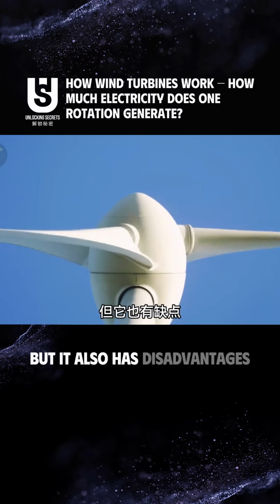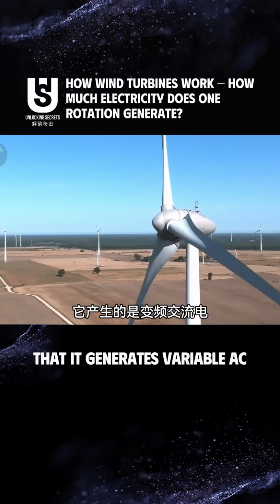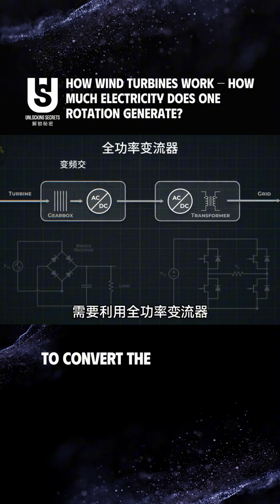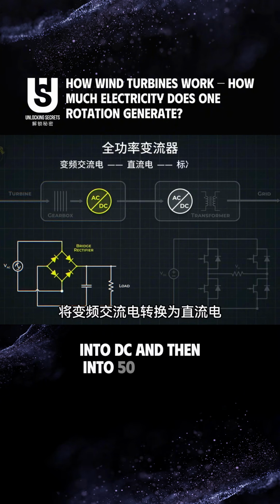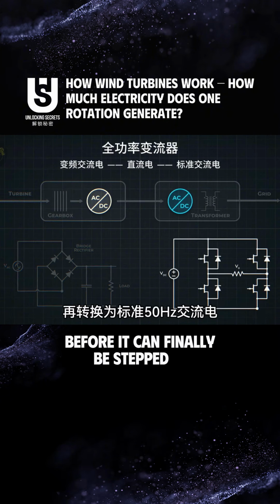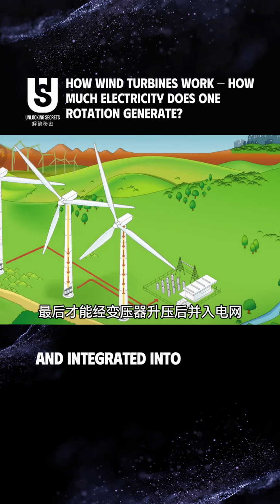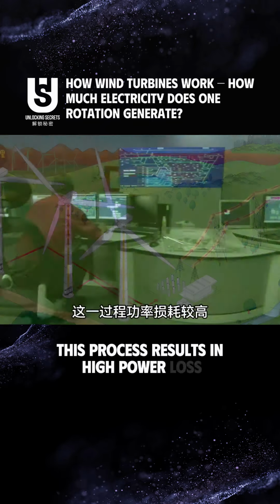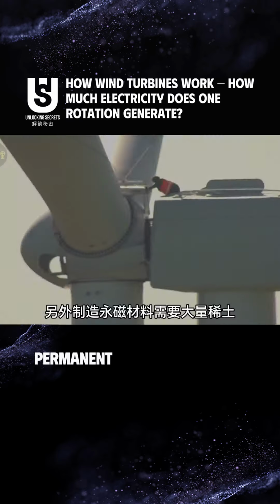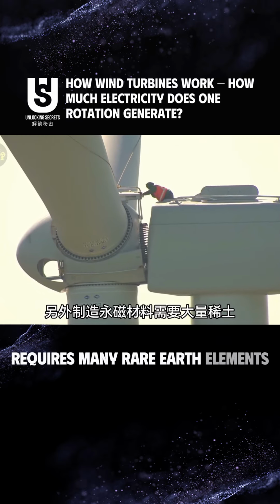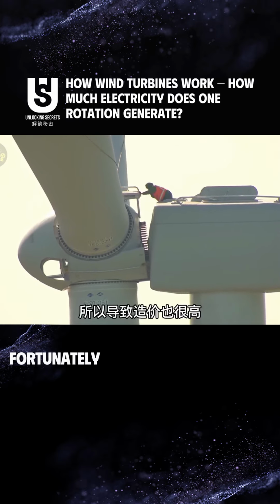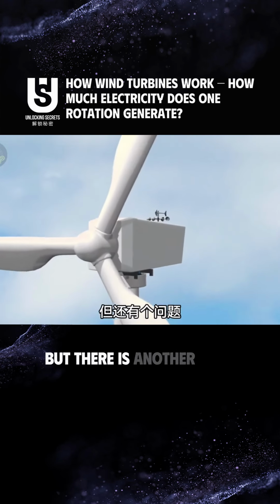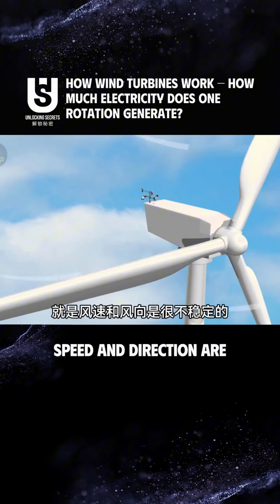But it also has disadvantages: it generates variable AC, which requires the use of a converter to convert the variable AC into DC and then into 50 Hz AC before it can finally be stepped up by a transformer and integrated into the grid. This process results in high power loss. Additionally, manufacturing permanent magnet materials requires many rare earth elements, which makes the cost very high. Fortunately, our country controls 90% of the global supply of rare earth elements. But there is another issue, which is that wind speed and direction are very unstable.